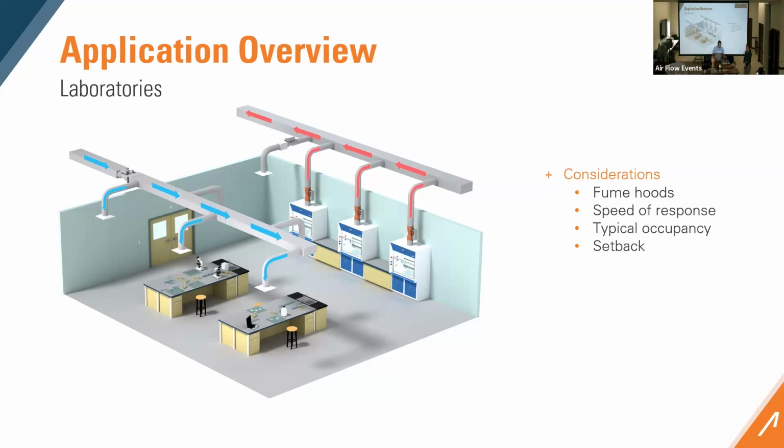The LMX, going back to that really quickly, all it does is give you an output signal that's linear to the flow. So you have your 2 volt, which is your minimum flow, to your 10 volt, which is your maximum flow. What you would do to control that is send a 2 to 10 volt signal to the actuator itself. The actuator would move it. So 2 volts to the actuator may or may not be the minimum flow that's output by the LMX. You can see when you move it to a position, the potentiometer in here reads the position of that arm. So this may be 8 volts. The voltage of the potentiometer goes to the LMX and that outputs a voltage that is going to be your flow. And on here, we don't actually have it, but there's usually a sticker with a graph of the flow.